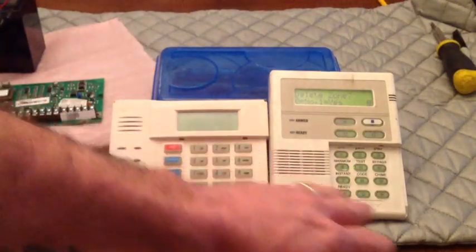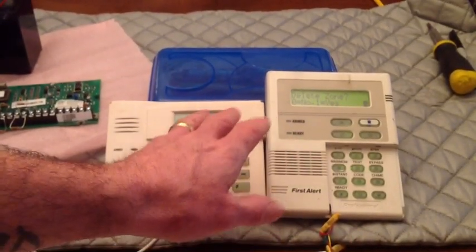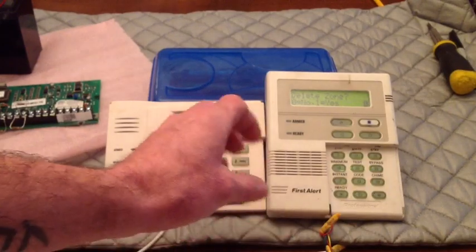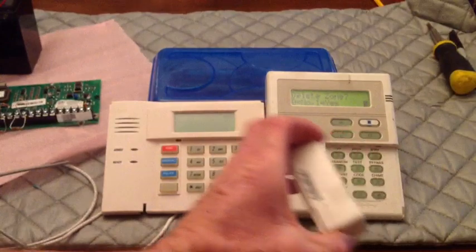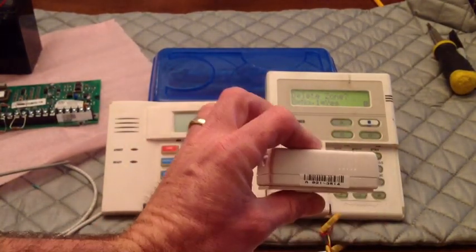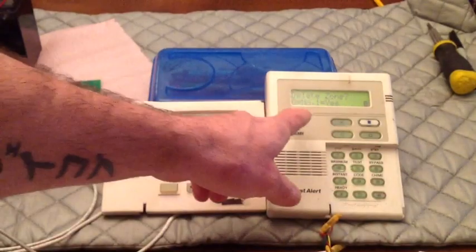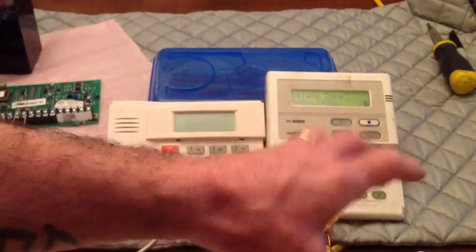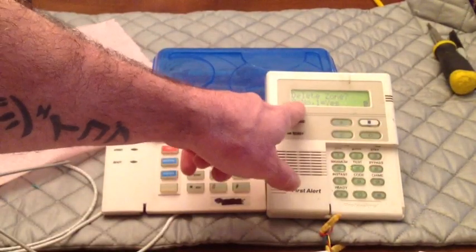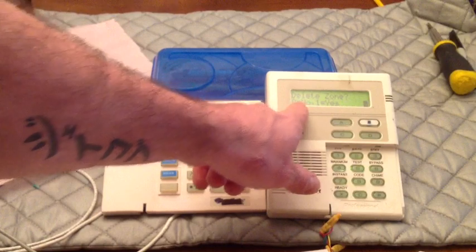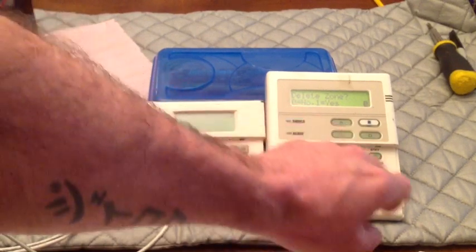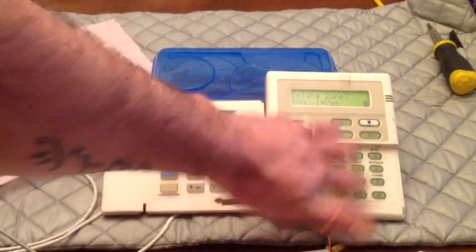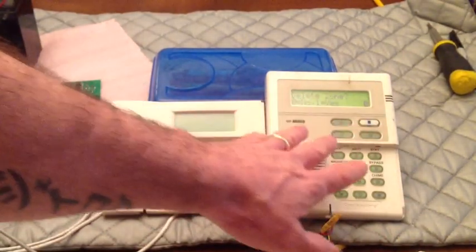If you hit delete, it will wipe out information that you'd put in there. Let's just say that I had a wireless zone. And this is where I think it comes into play more than anything. Say if I had a wireless zone and I had each wireless zone has a little serial number on it. Let's say I had a wireless zone with this serial number in it. If I wanted to just disable the zone, say it had a low battery, whatever, and I just want to disable the zone, you'd go in here, put 0, 0 as the zone type, and it says delete. You just hit star or no. If I wanted to disable, that's just disable. Because later on, I could come back and put a 3 or 1 or whatever I wanted to in there as a zone type and bring it back to life.